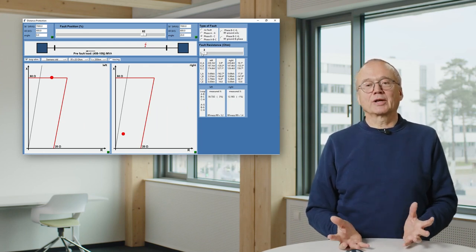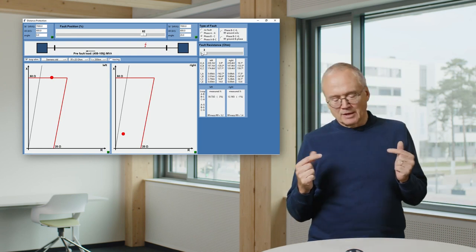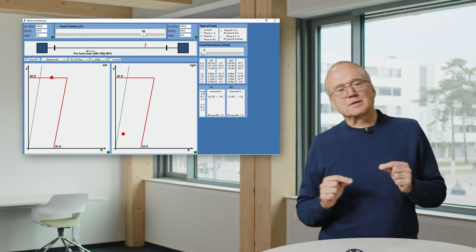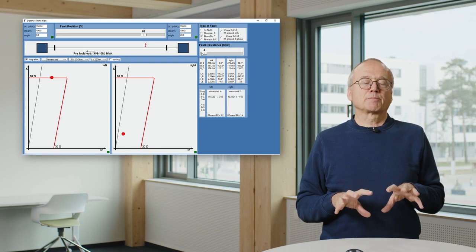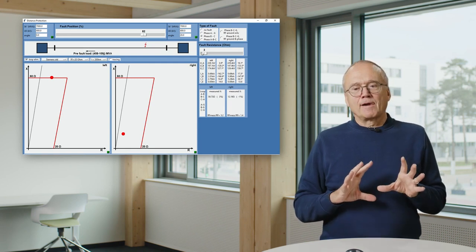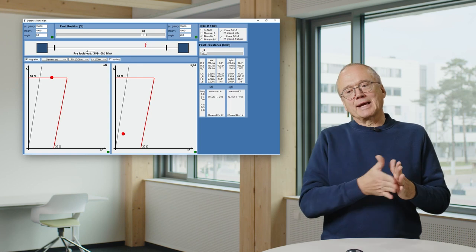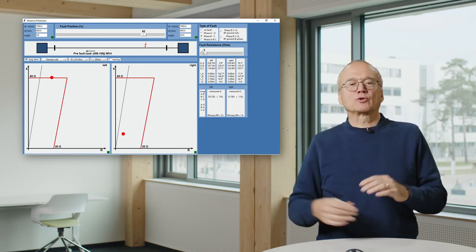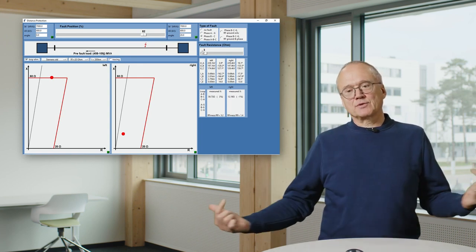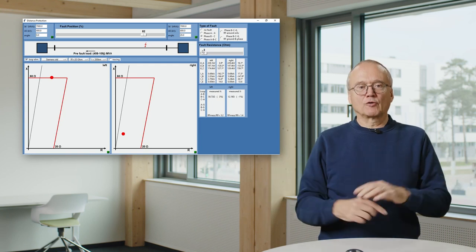be outside the characteristic. That means fault resistances in distance protection have impacts in 2 directions. On one hand, this movement to the right depends on the ratio of the current of both sides.